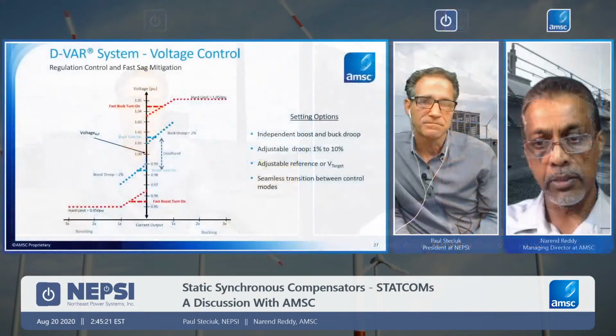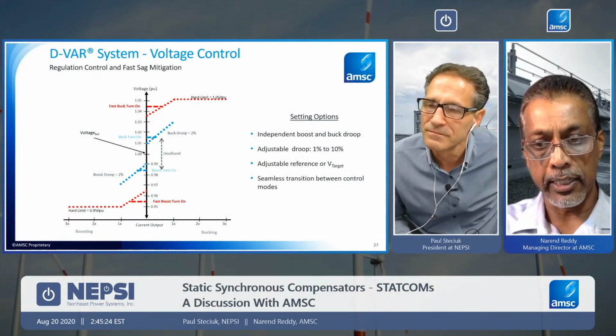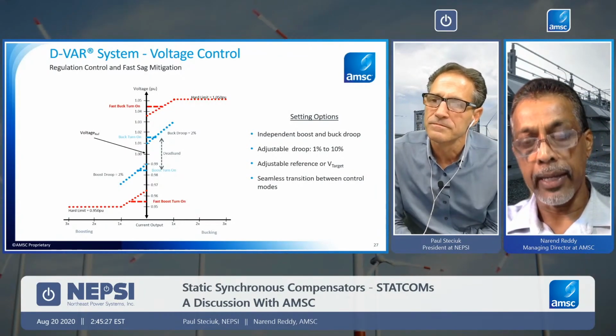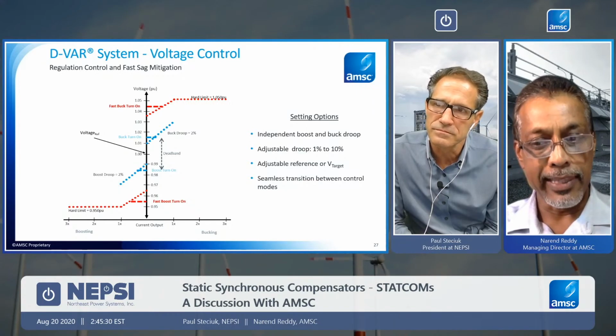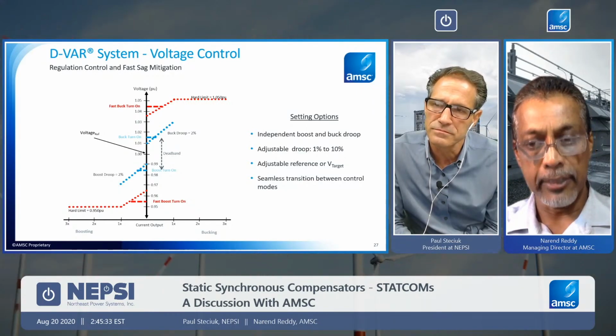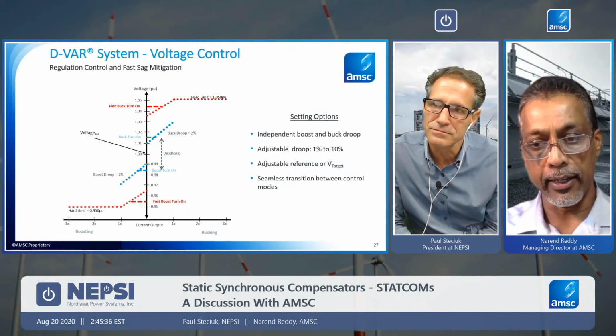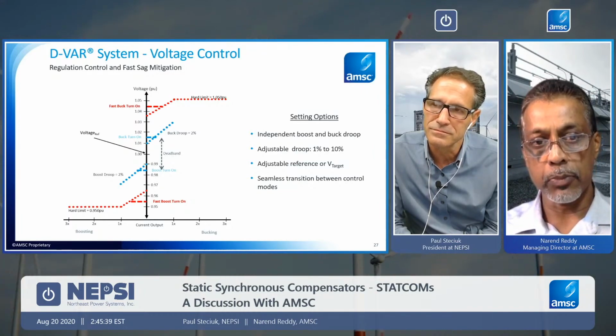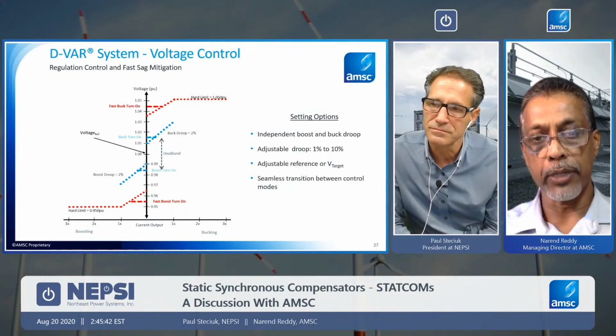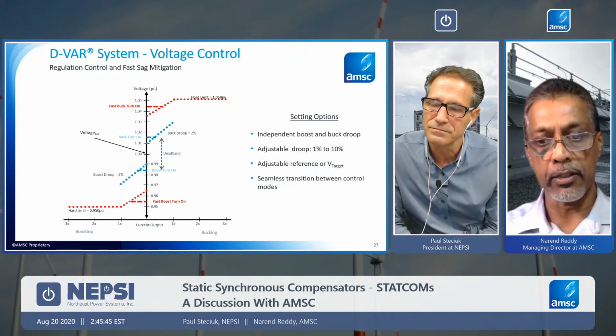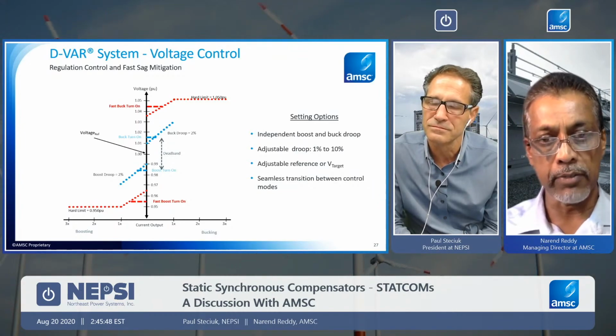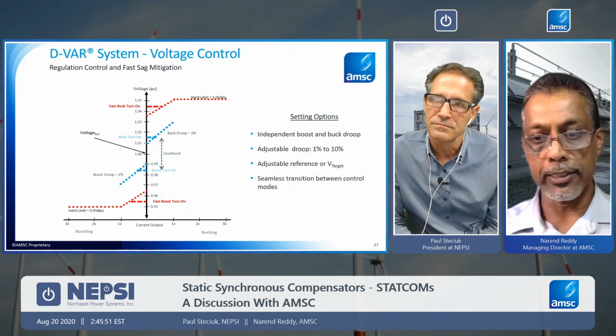Yeah. Now, one of the things I would point out here, like I mentioned, there are two control regimes in operation. In this blue region, which is what we call the normal voltage range, you have your steady-state droops in play, and the speed of response in that realm is going to be different than what you need under a fault condition. Because it's something that changes over a longer period of time, it might be time of day, or load changes over the course of the day or week, you don't need to respond on a cycle-by-cycle basis.